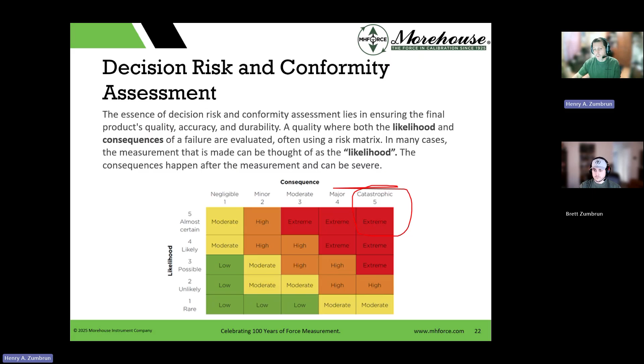Decision rules are not required. I mean, they are required if you want to make a conformity assessment. For statements of conformity, labs must document the decision rule employed, taking into account false accept and false reject. If the rule isn't standard, it must be agreed with the customer. Guard banding is optional. It's one way to implement the decision rule.